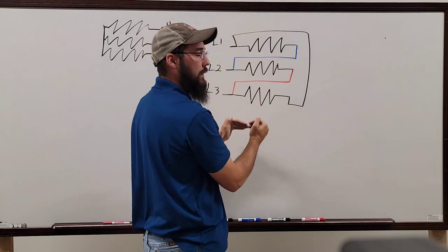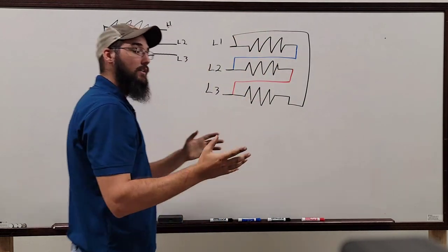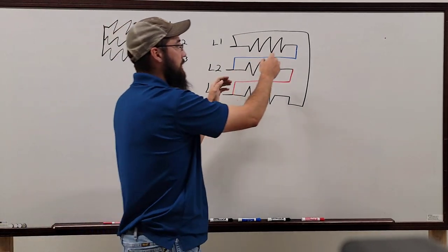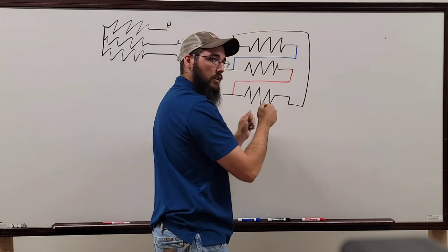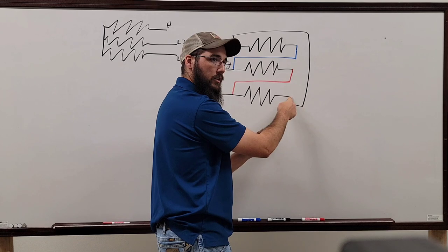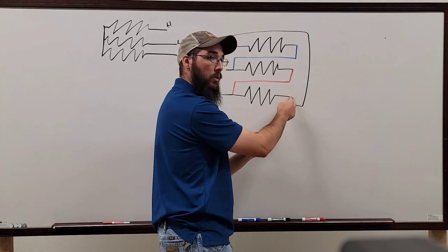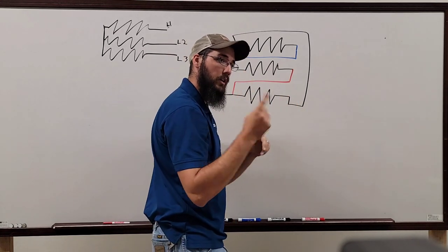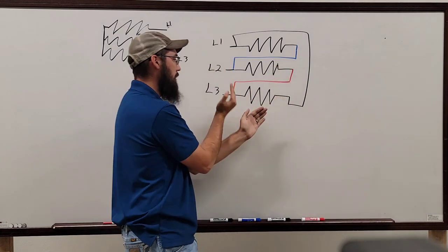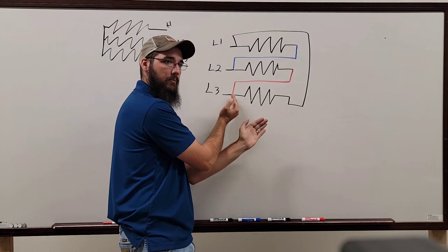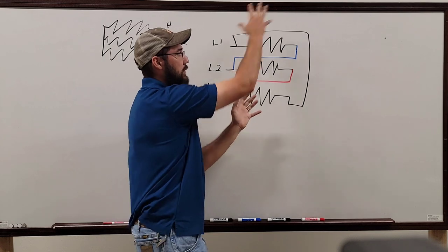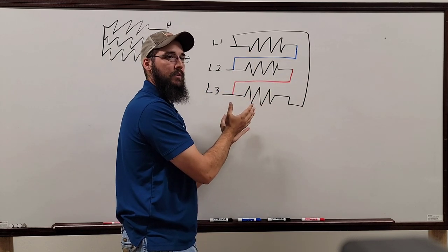So it's three independent completed circuits, but instead of them having just a simplified bar in the unit, these lines are literal wires, and you have a double termination point. So you've got two heaters hooked up to this one point, but each line is flowing to two different heaters. They're making a termination spot right there. So that is where the wire scramble happens.